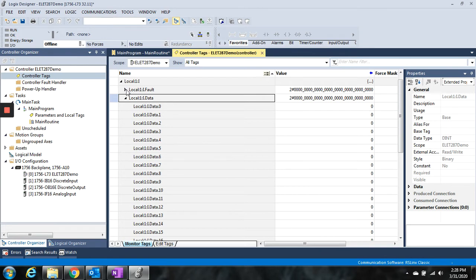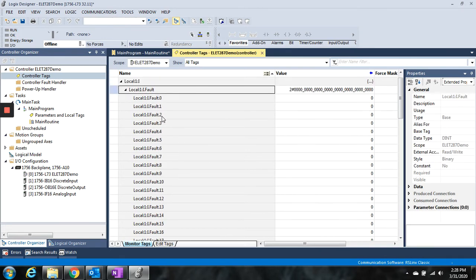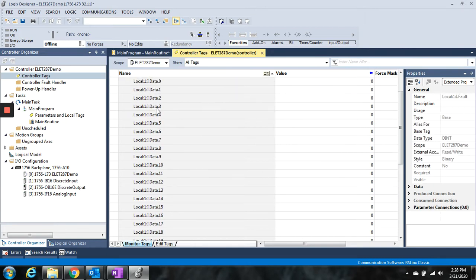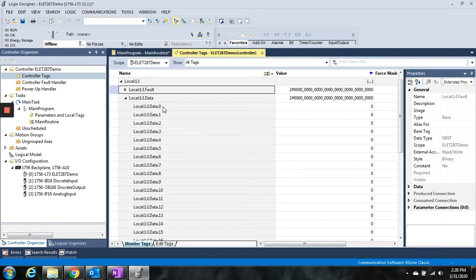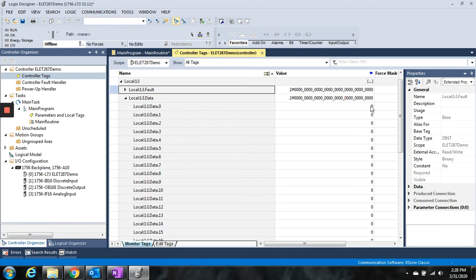Of course, fault would mean if there's any kind of particular fault with those cards, we get that there. Data would refer to the data. So .0, .1, .2 would refer to bits 0, 1, 2, or inputs 0, 1, 2 on the card. So if I had a switch wired to the first input, then that would be data.0, and my 0 or my 1 would show up right here.